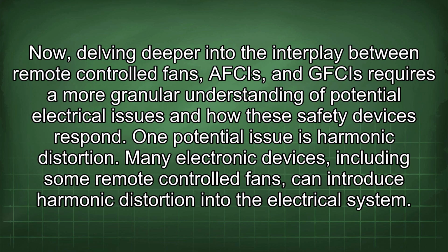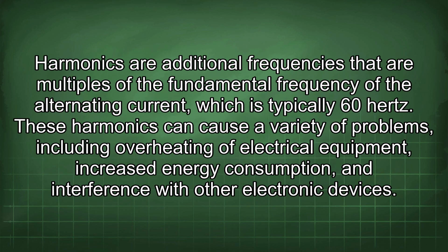Now, delving deeper into the interplay between remote-controlled fans, AFCIs and GFCIs requires a more granular understanding of potential electrical issues and how these safety devices respond. One potential issue is harmonic distortion. Many electronic devices, including some remote-controlled fans, can introduce harmonic distortion into the electrical system. Harmonics are additional frequencies that are multiples of the fundamental frequency of the alternating current, which is typically 60 Hz.